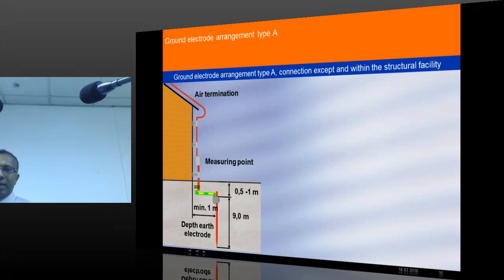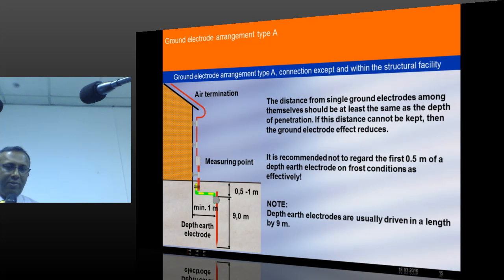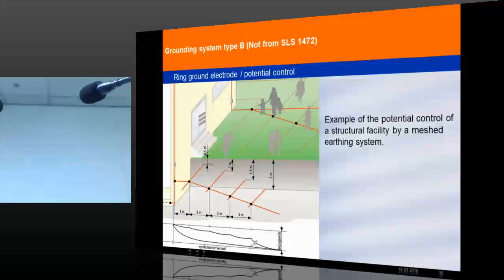This is the interconnection of type A, how to achieve type A earthing. I skip a few of the slides because we have so many other things to discuss. Yeah, this is about the ring electrode. I asked a question, how to protect people outside the building? Generally we don't consider it. Protection of people outside the building against step potential is also equally important. One of the methods explained, and this you cannot find in the IEC 62305 standard, I showed you some other standards.